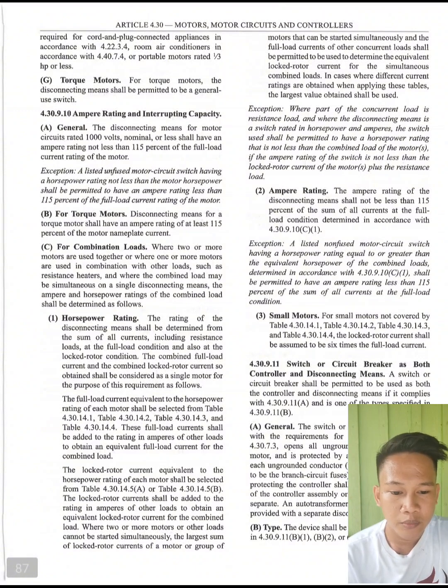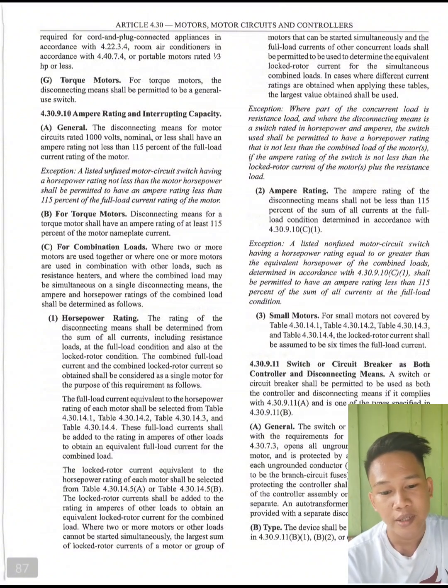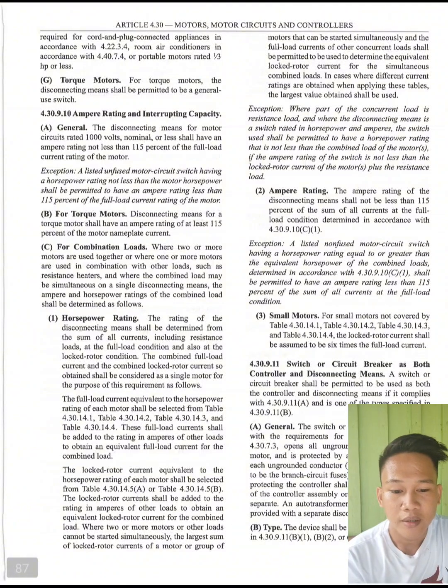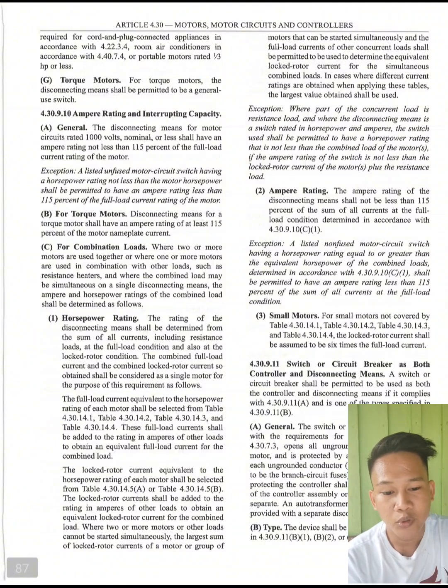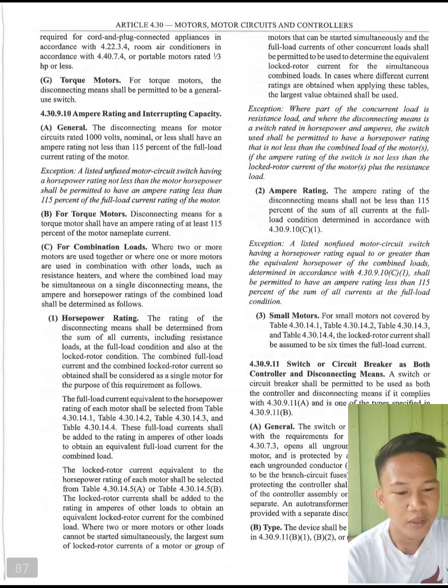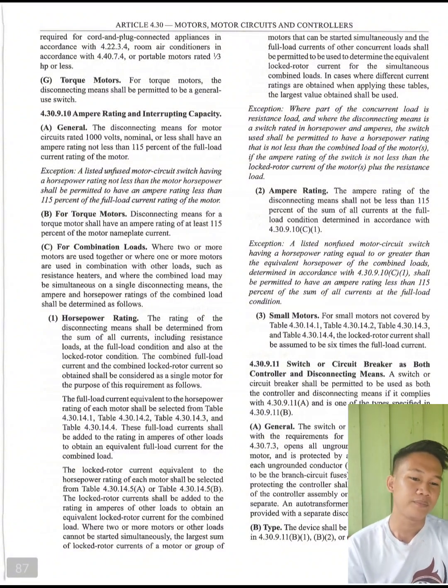So, where two or more motors or other loads cannot be started simultaneously, the largest sum of lock rotor currents of a motor or group of motors that can be started simultaneously and the full load currents of other concurrent loads shall be permitted to be used to determine the equivalent lock rotor current for the simultaneous combined loads. In cases where different current ratings are obtained when applying these tables, the largest value obtained shall be used.